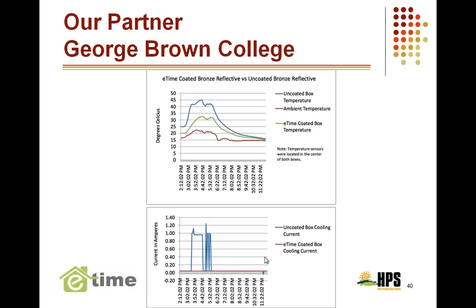This pushed a lot of heat away. It again fell within the 11-degree range, but the real telltale on this was the energy use. We were able to maintain a set point temperature where the uncoated box couldn't, and the cooling load had to be pushed. There was never an opportunity for our cooling load to come on.